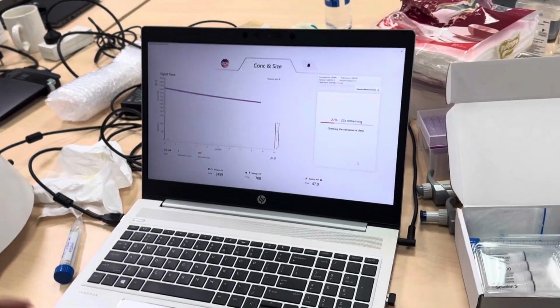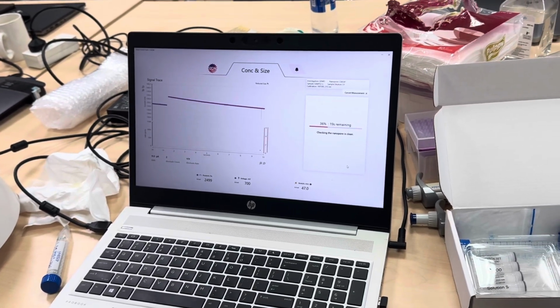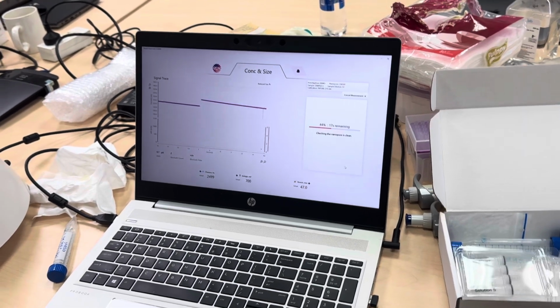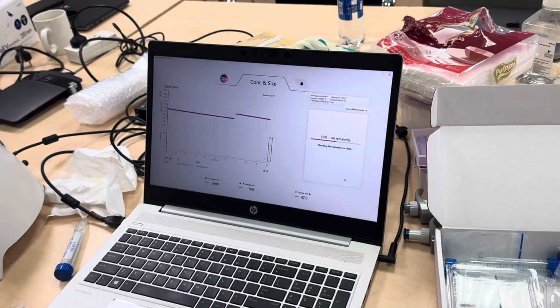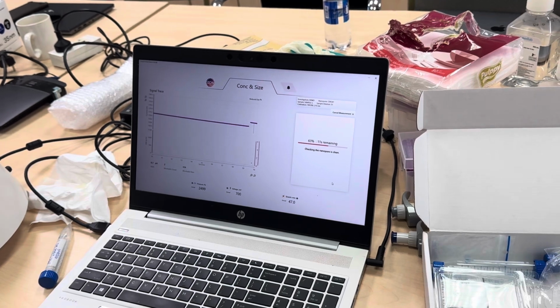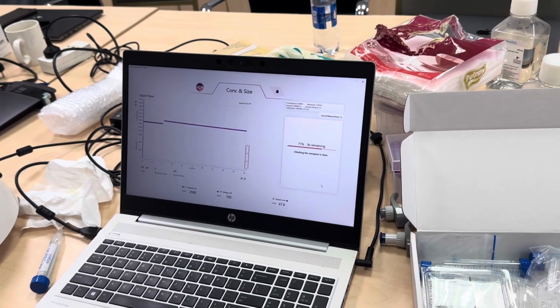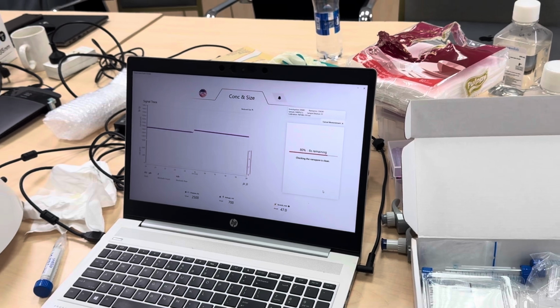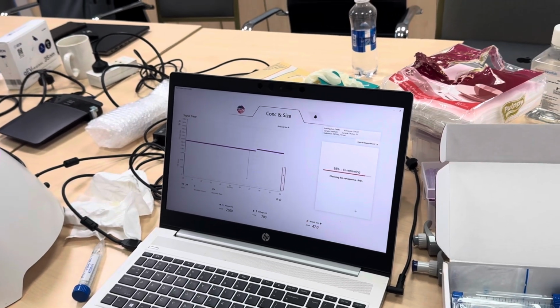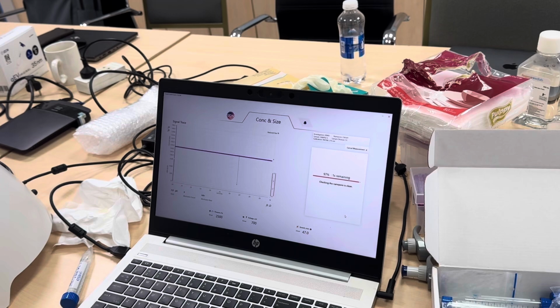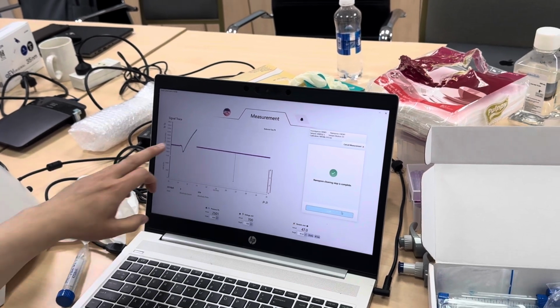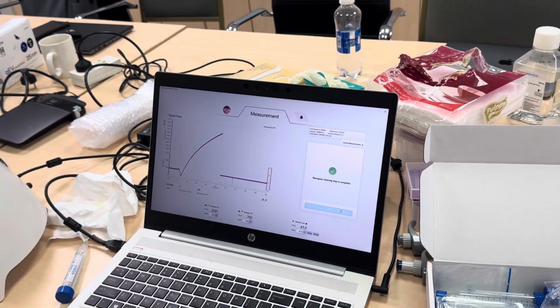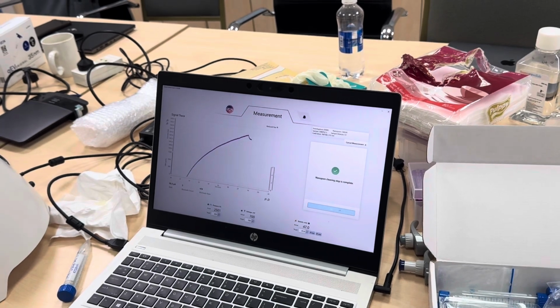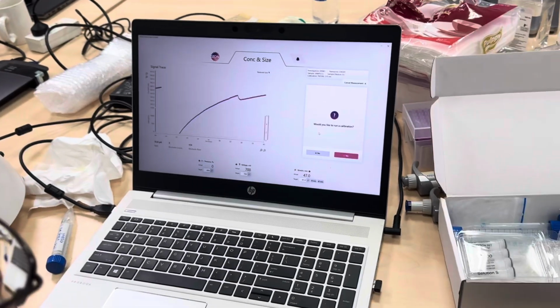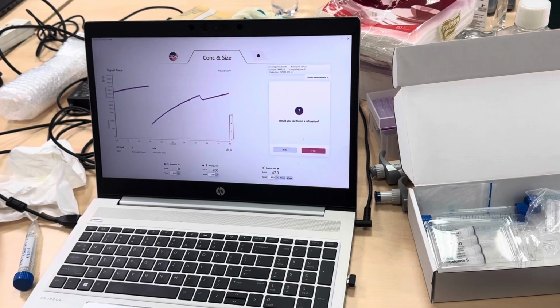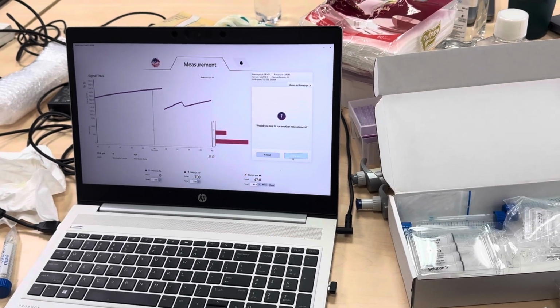It's just this procedure. First do the calibration, then wash the nanopore, load the first sample, finish the measurement, clean the sample, clean the nanopore, load the second sample, and continue. So you see the nanopore is quite clean, and the report says clean, because I just did that. Usually you wash it, and then it will ask whether you want another calibration or just run another sample. I don't want one, so I just run another measurement.